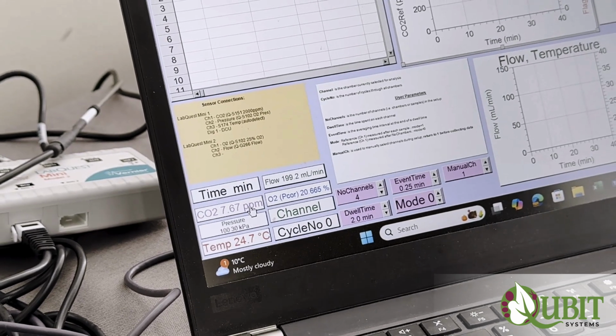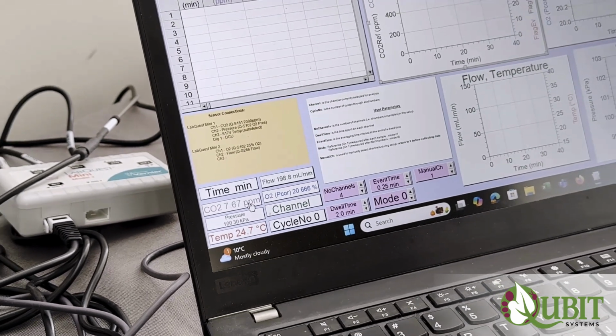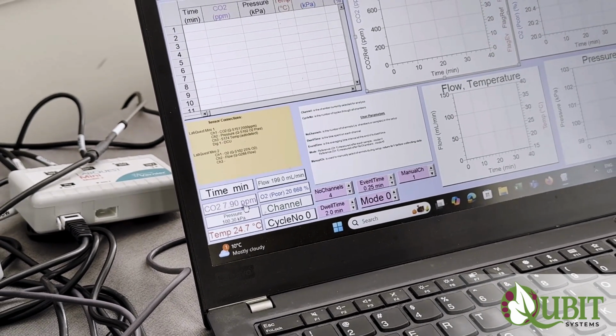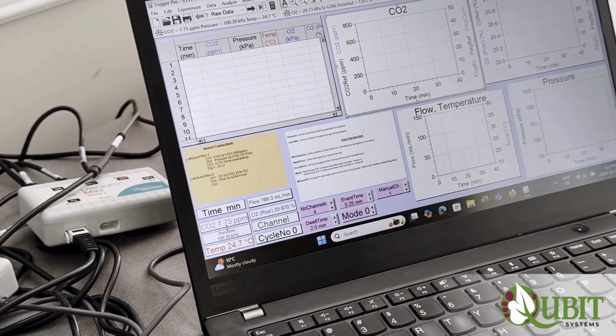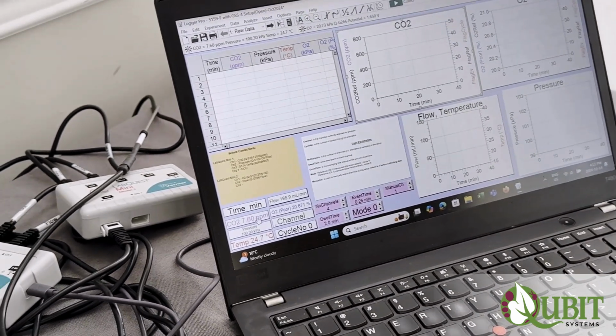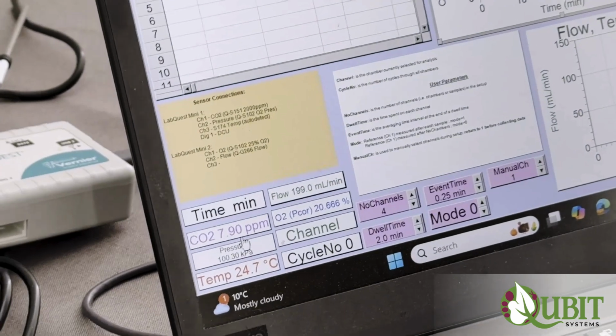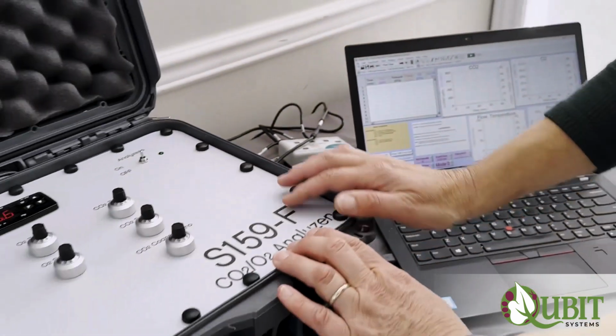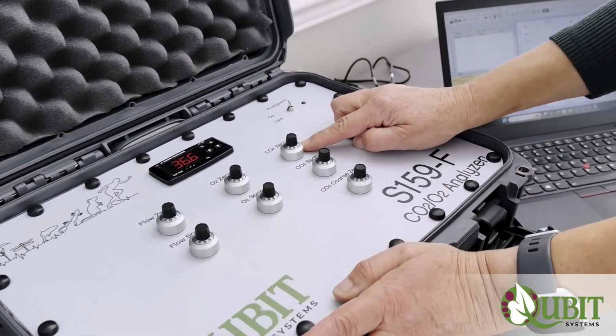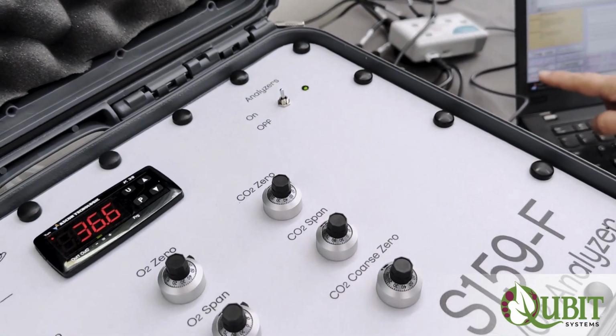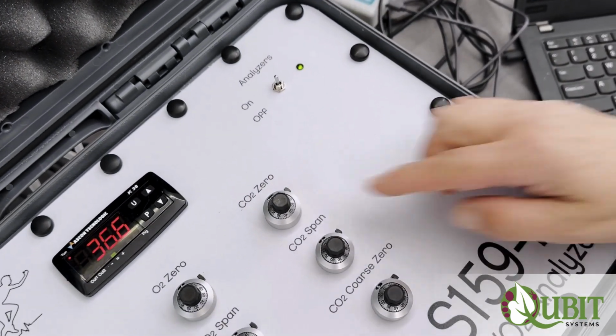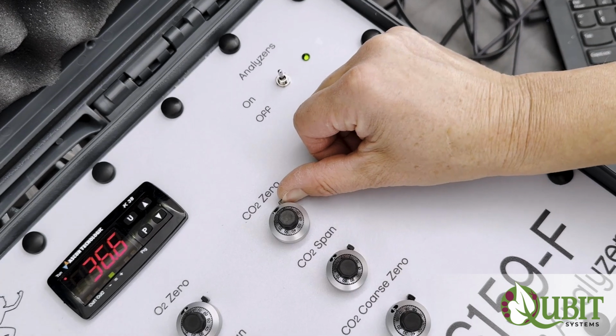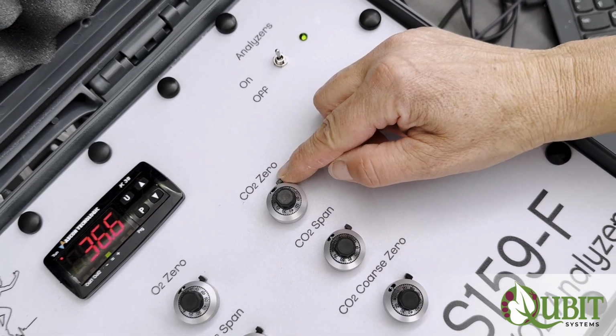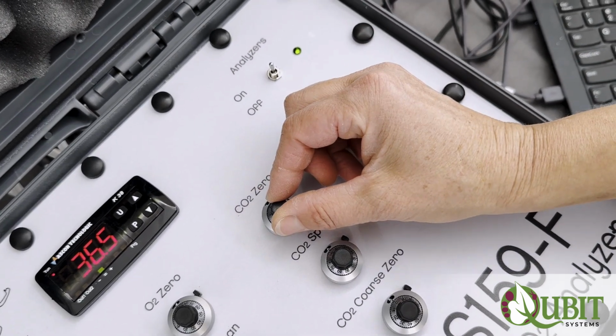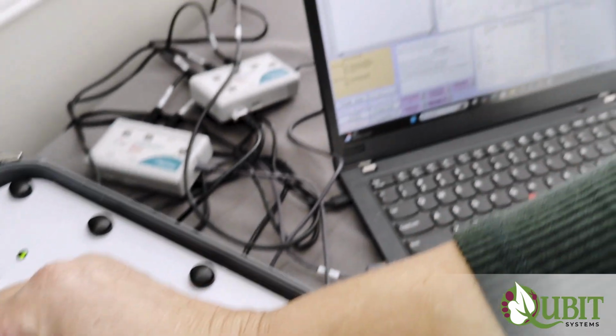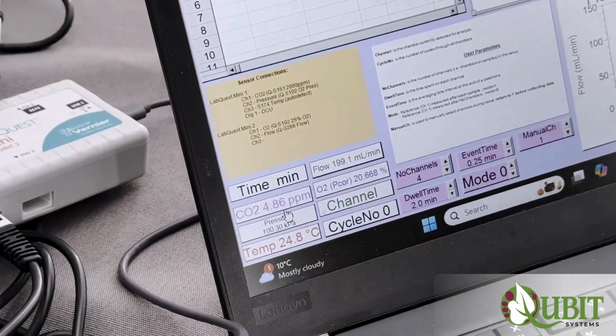Usually it takes 2 to 5 minutes for that to stabilize. We've already been running gas for a few minutes, so we're more or less there. And you can see that this is not reading 0, but it's reading 7 point something. So we have to go up here and adjust this CO2 zero while looking at software. To adjust the CO2 zero, you have to first release the knob by pushing it up, and then turning it anti-clockwise will reduce the reading, and clockwise will increase it.